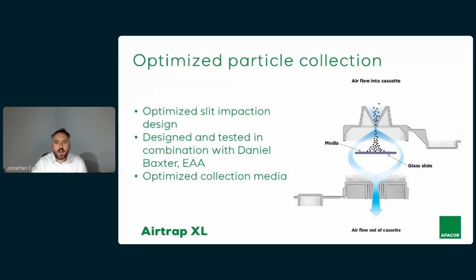So now if we take a closer look inside the cassette. On the right here, we've got a schematic diagram, a cross-section through the cassette, showing the cassette in use with airflow and particulate collection taking place. First of all, you can see that the top cap, the inlet cap, is open. The blue line indicates the airflow as it travels through the cassette, passing around the glass, the airflow being drawn in by the pump that you're using it on.